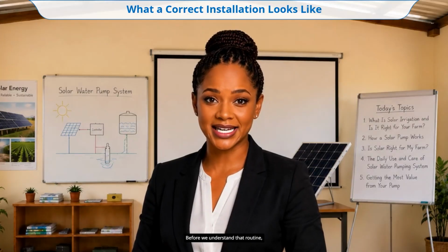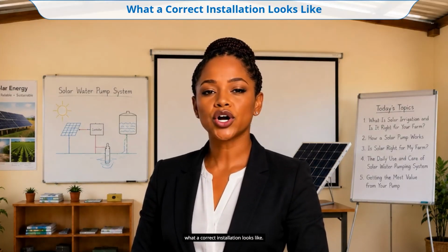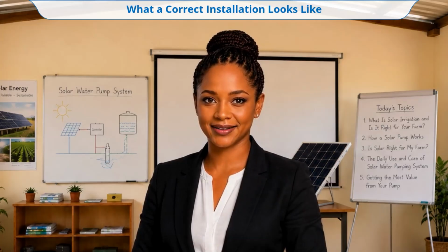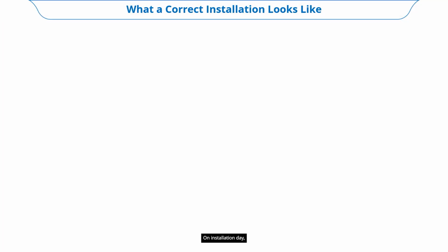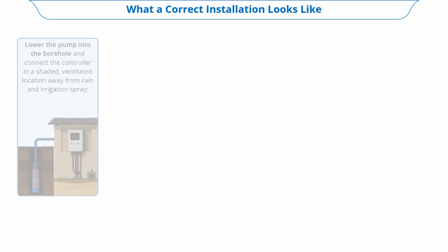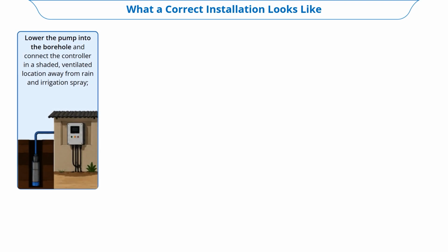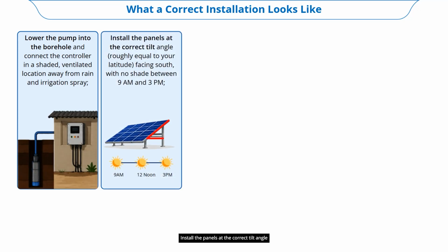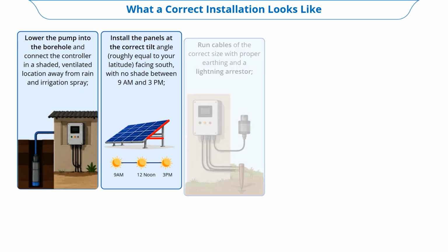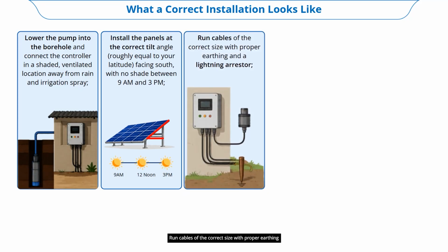Before we understand that routine, it is important to know what a correct installation looks like. On installation day, your responsible dealer will lower the pump into the borehole and connect the controller in a shaded, ventilated location away from rain and irrigation spray. Install the panels at the correct tilt angle, roughly equal to your latitude, facing south, with no shade between 9 a.m. and 3 p.m. Run cables of the correct size with proper earthing and a lightning arrestor.